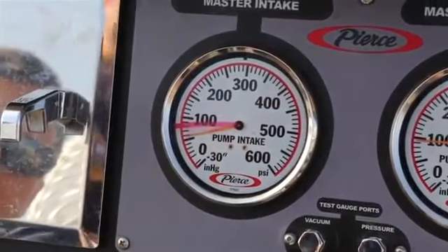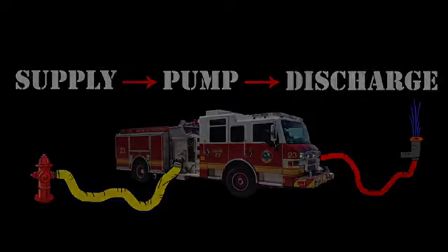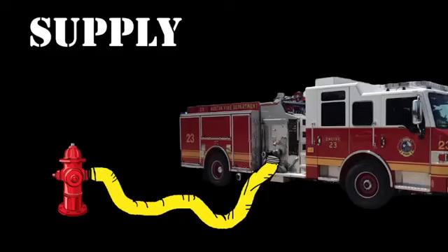Whenever we encounter a problem during a pump operation, we use the progression supply, pump, discharge. This is a quick and easy to remember method for analyzing and assessing the issue in a high stress environment. So we'll start with supply problems.